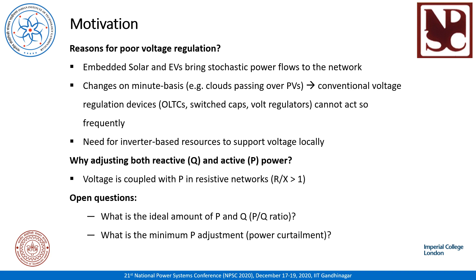In order to find these answers, let us explore how the PV node voltage changes with the P and Q value of the PV inverter. To mathematically obtain the relation between the voltage and the P and Q of the PV inverter, a single node grid connected PV inverter system is considered. The voltage drop across the line is given by delta V is equal to (PL minus PPV) into R plus (QL minus QPV) into X upon mod of V2, where PL and QL are the load active and reactive power demand. From this equation, for delta V to be minimum, the inverter should operate at nominal capacity S nominal.